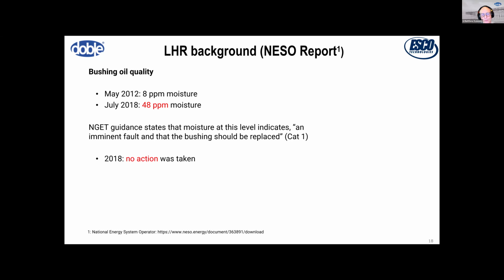Well, unfortunately, they took no action because this was a category 1. And the question is, how many category 1s did they have that day in their system that was modeled up to be a 1? 60. So it was one of 60 super high urgent alarms going off. One of the sayings is that if everything is urgent, then nothing is. Unfortunately, you kind of fall into that trap.